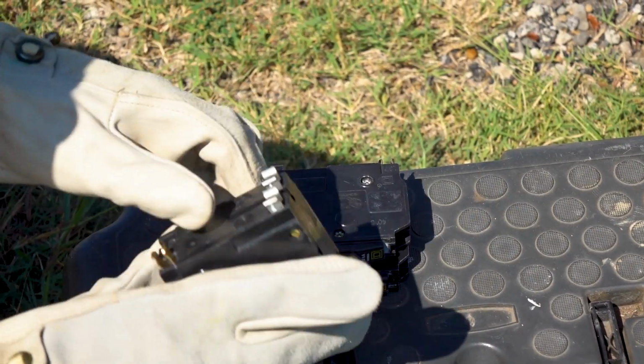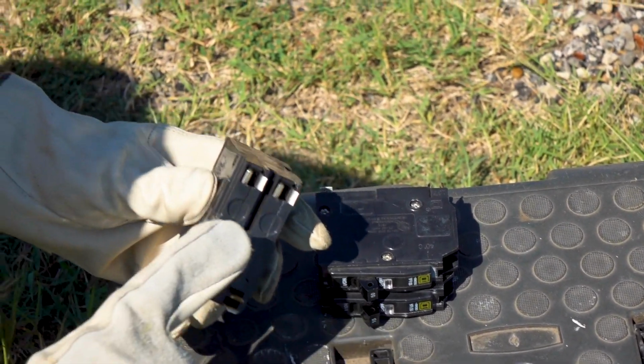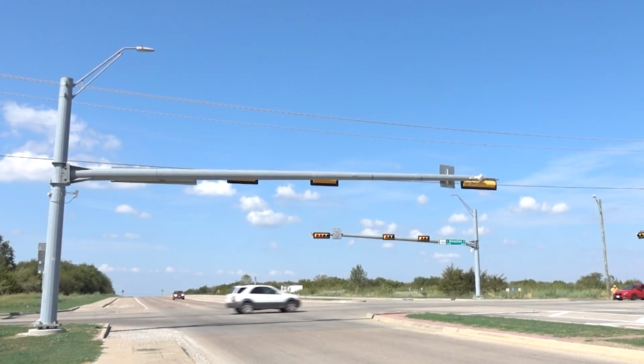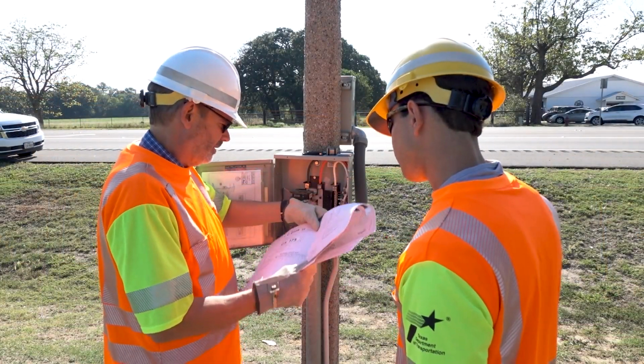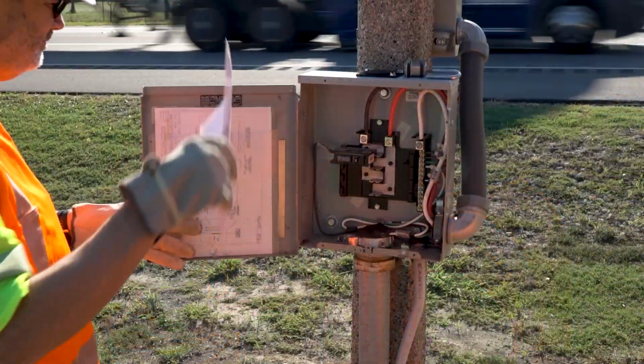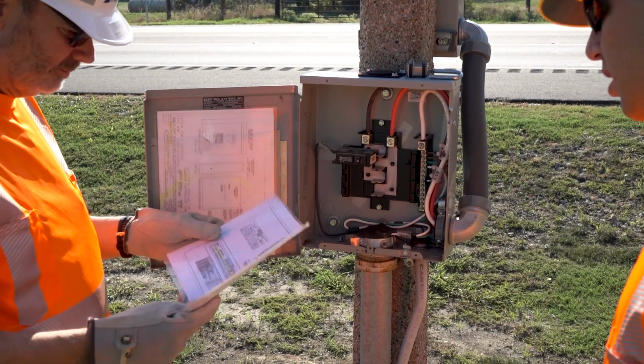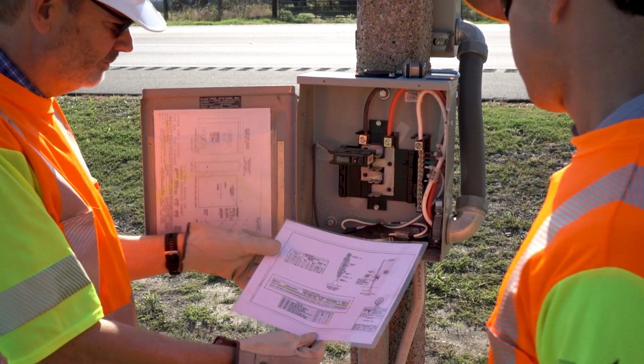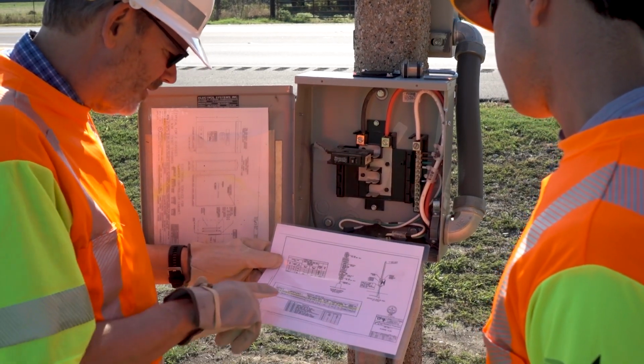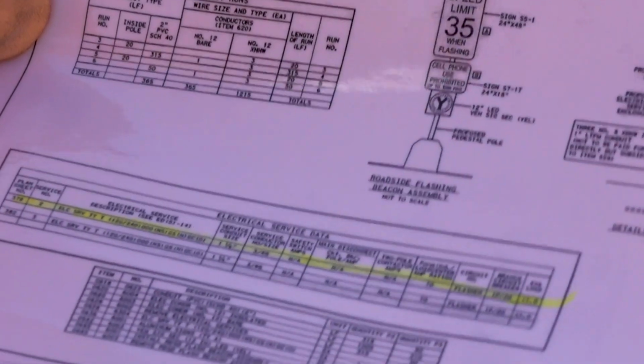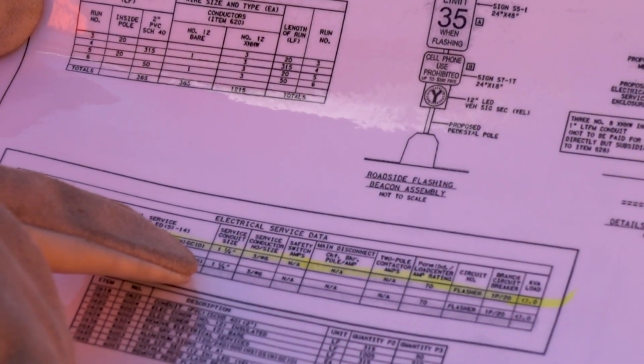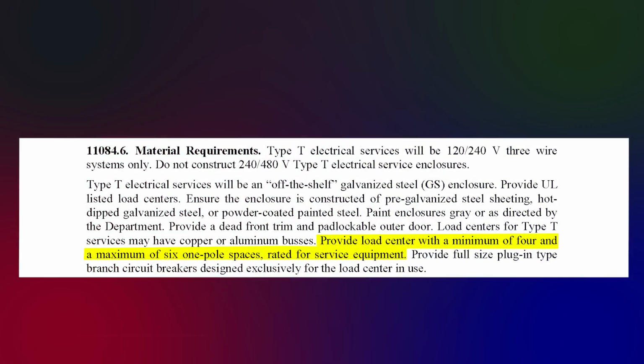A breaker that fills 2 slots is called a two-pole breaker and will serve a 240-volt load, such as a luminaire mounted on a traffic signal pole. The inspector will need to review the plans and find the electrical service data chart to determine the exact number and size of 1- and 2-pole breakers to be installed by the contractor. It is not necessary for all the load center slots to have a breaker installed into them.